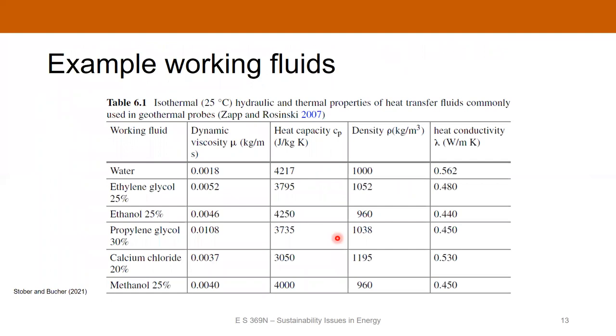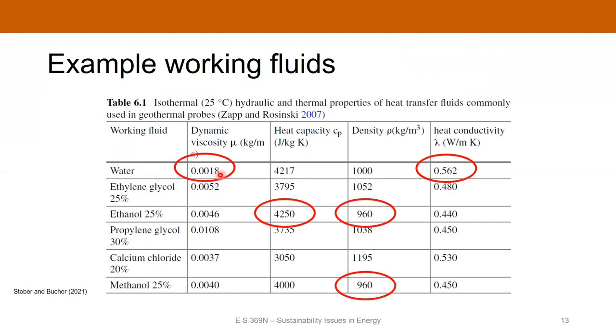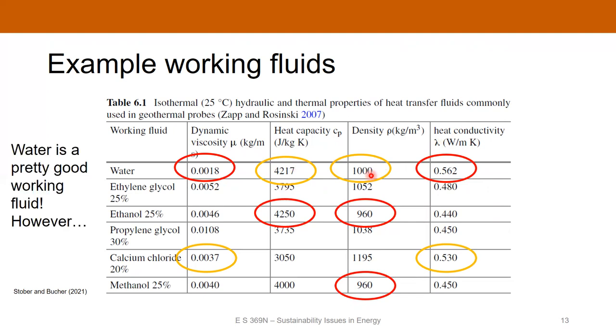Looking at simple working fluids that don't undergo phase change — water and various antifreeze mixtures like ethylene glycol, propylene glycol, ethanol, methanol, and calcium chloride — water has the lowest viscosity and the highest thermal conductivity. A 25% ethanol solution has the highest heat capacity and lowest density. Water actually performs pretty well overall: lowest viscosity, highest thermal conductivity, relatively high heat capacity, and a middle-of-the-road density, making it an excellent working fluid candidate.